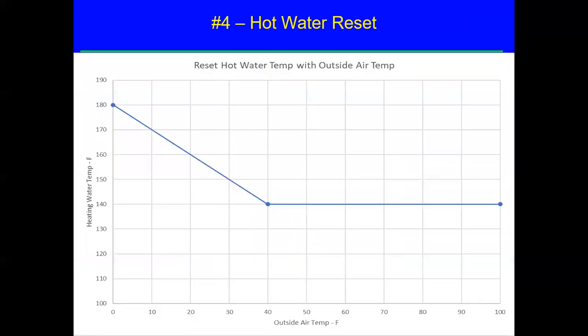I just added this slide today, but it illustrates a reset of hot water temperature with an outside air schedule. This is the kind of thing that engineers put on plans. You can see at 40 degrees outside, we're scheduled for 140 degree heating water temperature. As it gets colder, we simply ramp that up. These are typically pretty close to linear. We're showing it at zero, it's going to 180 degrees. The engineer can select whatever schedule he wants. You could take it to 180 at 10 degrees if you wanted to, and then just maintain it there as it gets colder, if that's sufficient heat to heat your building. And we show it at greater than 50.